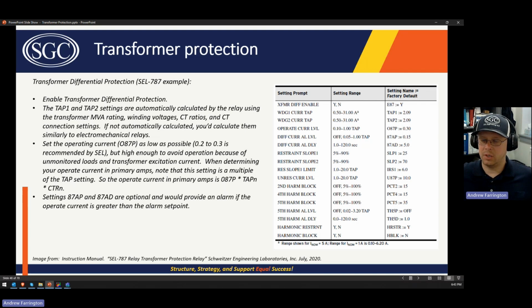And this is something that if you're ever setting a transformer differential relay for the first time, that the transformer is going to service, so you've set up the CT ratios and the compensation settings, you should really try, if you're not there on site yourself, to get the commissioning engineer to look at the operate current on the relay after it's in service and servicing load, because the operate current should be essentially zero. Ideally, it's zero. There may be a little bit because of mismatch or inaccuracies in the CT, the tolerances within tolerance or whatever, right? So it should be zero or 0.01 per unit or something that's very low.